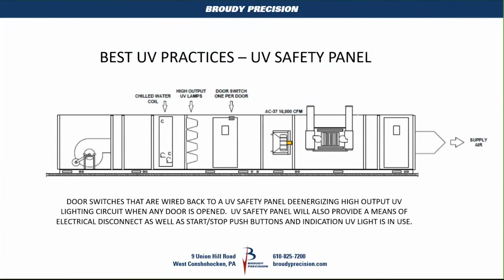There are often multiple doors. They'll see 2, 3, 4 doors per air handling unit compartment where these UV racks are installed. And we'll install magnetic switches that will wire back to a panel. And at any time a door is open, the lights are immediately turned off.